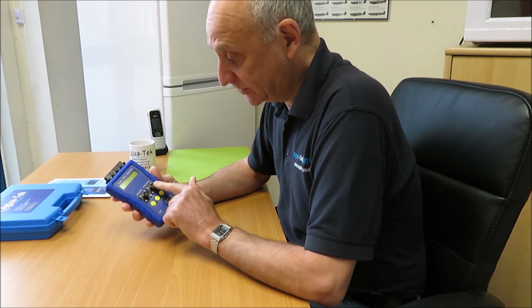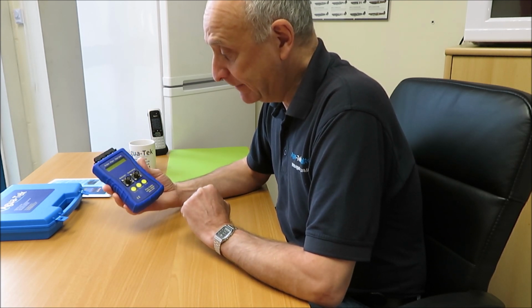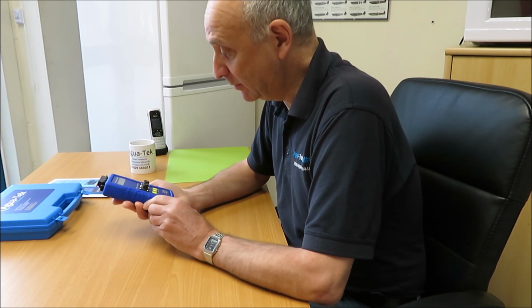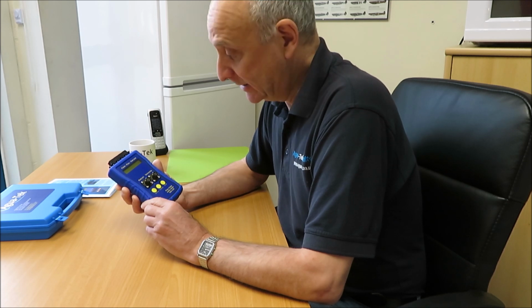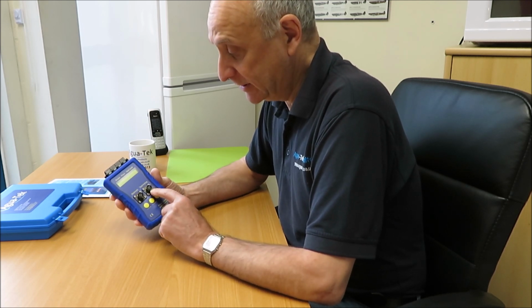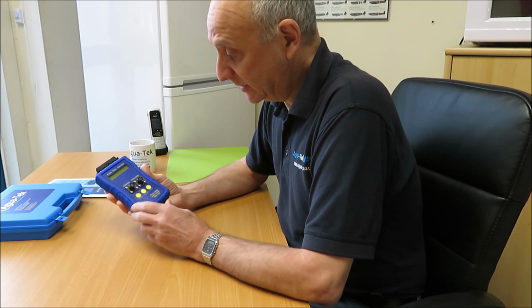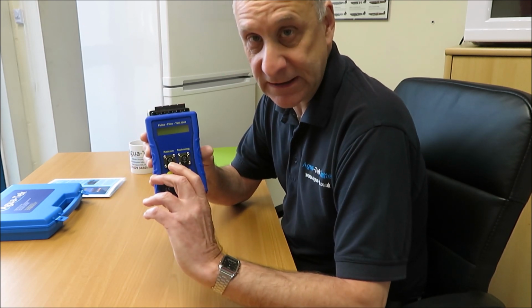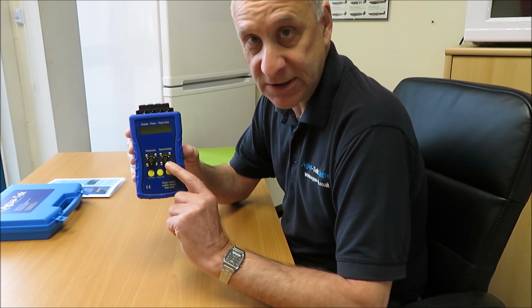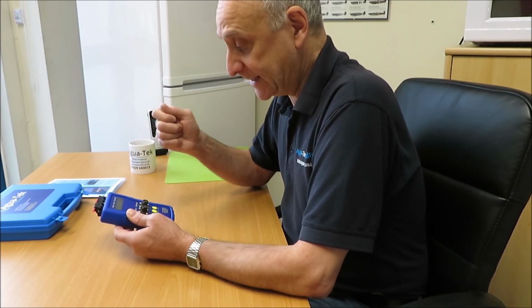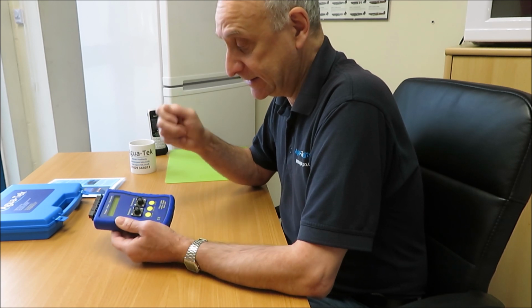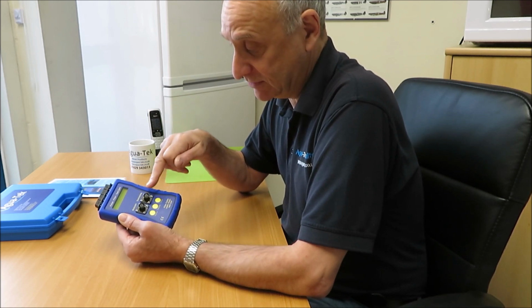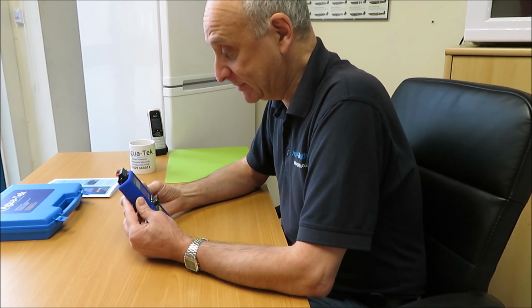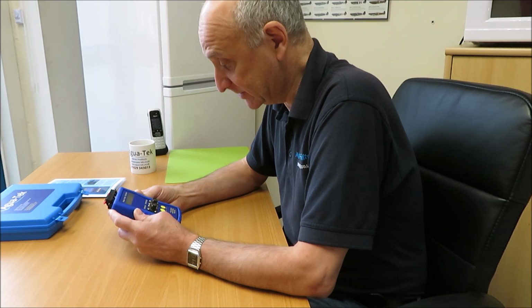However, the unit does come as standard with two connectors on the front panel, for the most common data loggers out there that you will probably be testing: the Halma Radcom data logger or the Technolog Cello data logger. The Radcom uses a 4-pin socket and the Technolog uses a 3-pin socket. So you could go out to site and find that there's a flow meter there, and there's an existing plug connector, Amphenol military style connector, that is capable of connecting into either of these two depending on which manufacturer it is. We can make adapter cables for Primayer units, things of that nature.